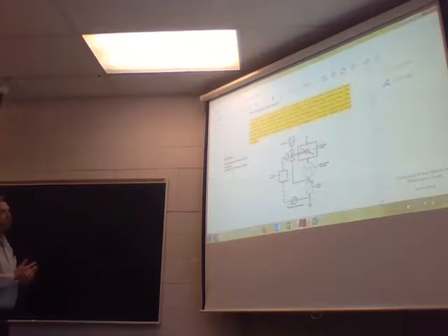Modulating inlet valve. This is real cool. We're going to need a pressure transmitter on it. This one we use quite often in power plants that I've worked. This method allows the compressor capacity to be adjusted to match the load demand. The pressure transmitter senses the discharge pressure. It sends a signal to a regulating valve controller, the controller positioner, and the inlet valve to the compressor, closing the inlet valve, reducing the mass flow to the air compressor, and so on.